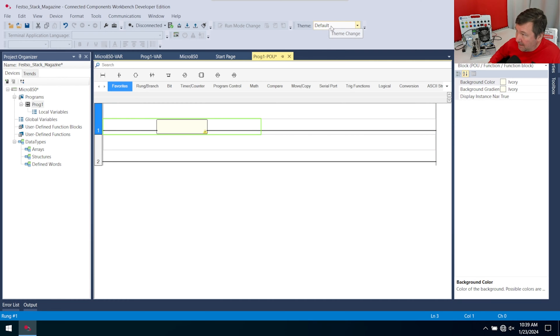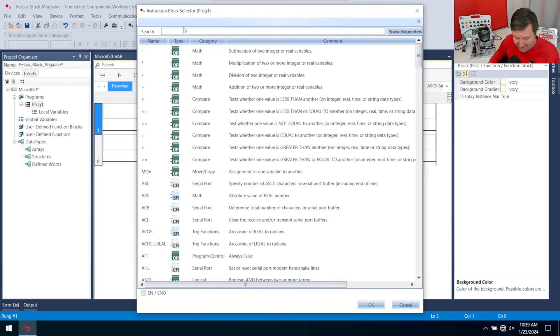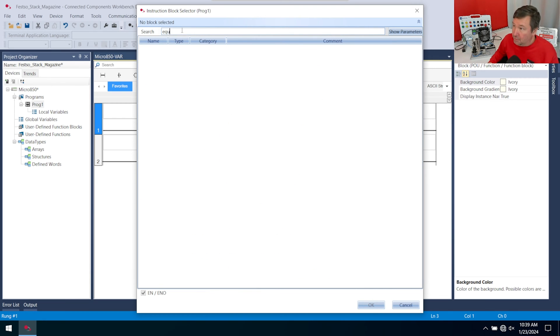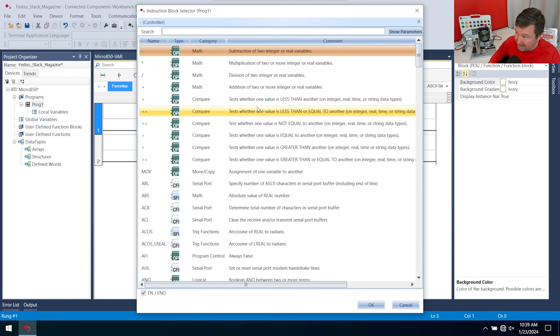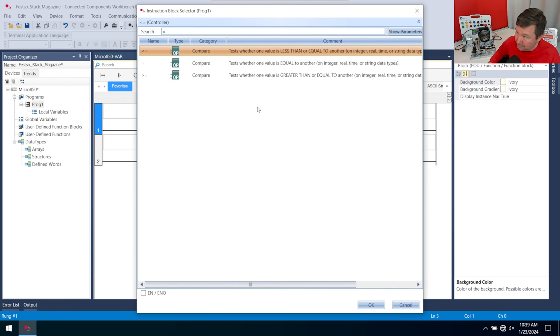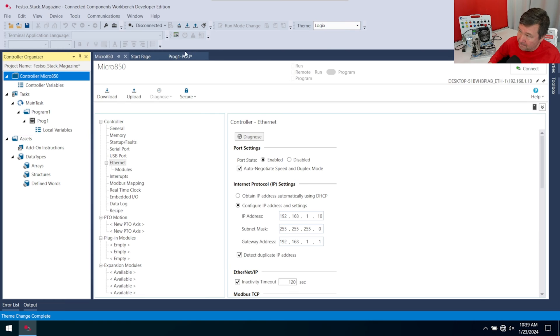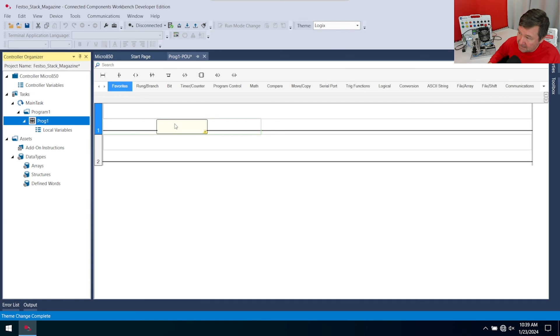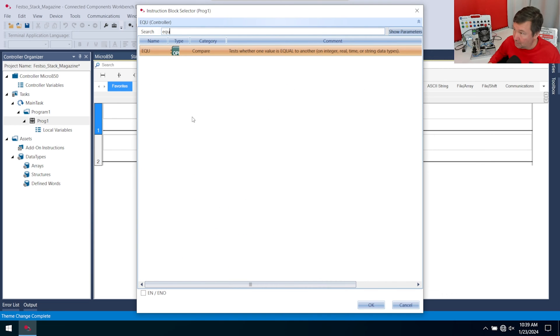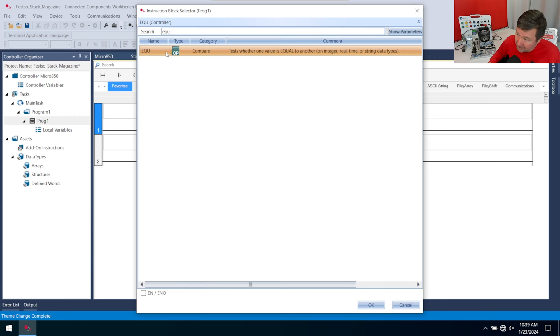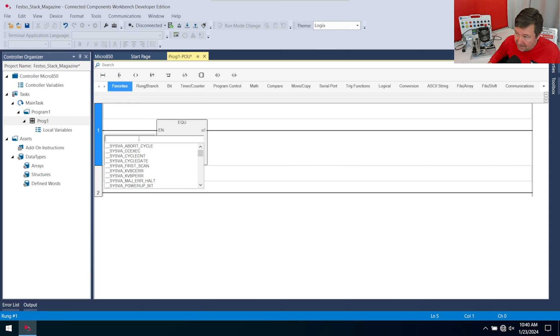We haven't really talked about this in this series, but we have two themes up here. If you're familiar with RSLogix 500 or Studio 5000, for equals you're thinking EQU. When you type it there, it's not going to be there because we're in the IEC 61131-3 standard. In its case, it is simply the equal sign. If you like the ladder ones better, we're going to go to this theme and hit the Logix theme. Now we can type EQU. Since my sequence video was done on these type of instructions, this is what I'm going to stick with.